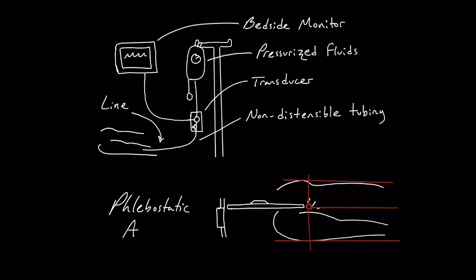Once leveled, open the transducer to air and zero the monitor to atmospheric pressure. This should be done before each use, with each change in patient position, and when there are questionable waveforms or readings.